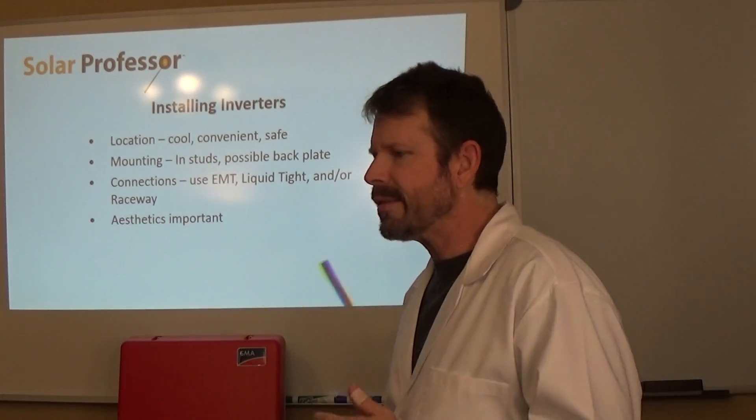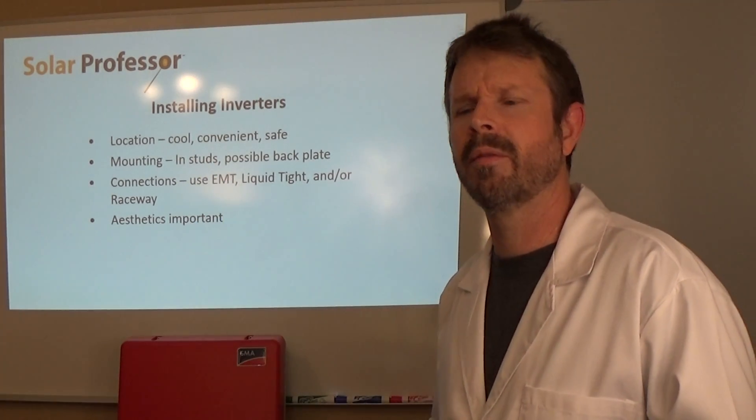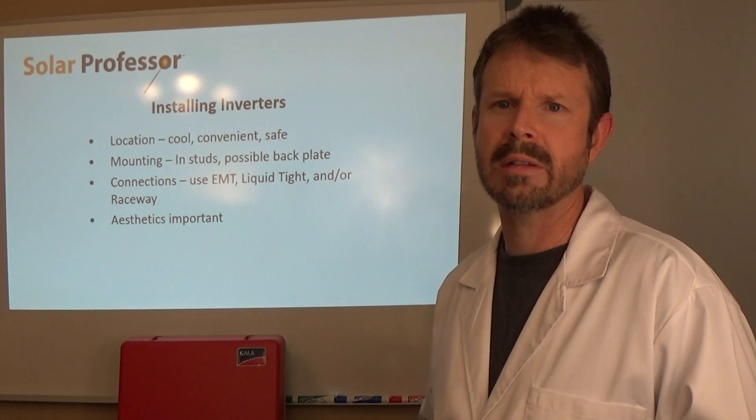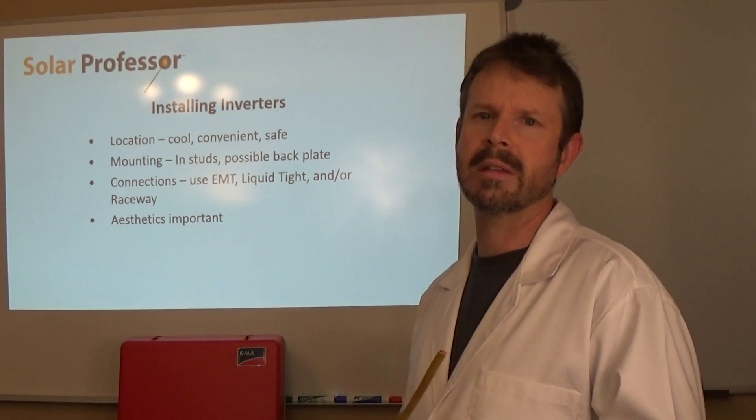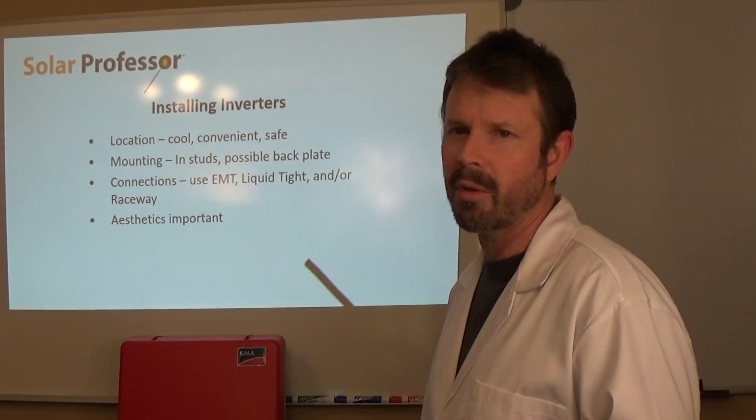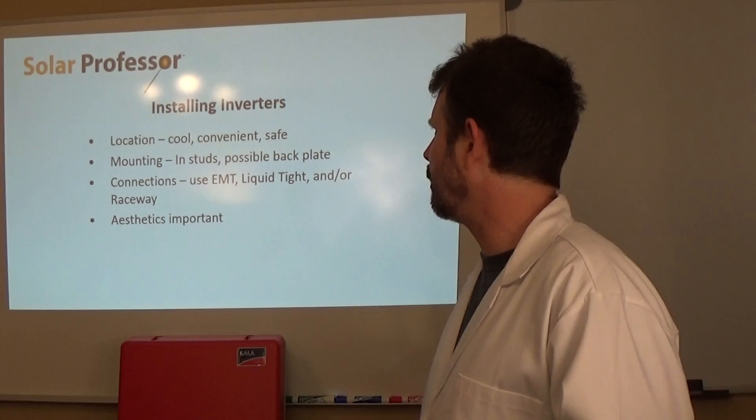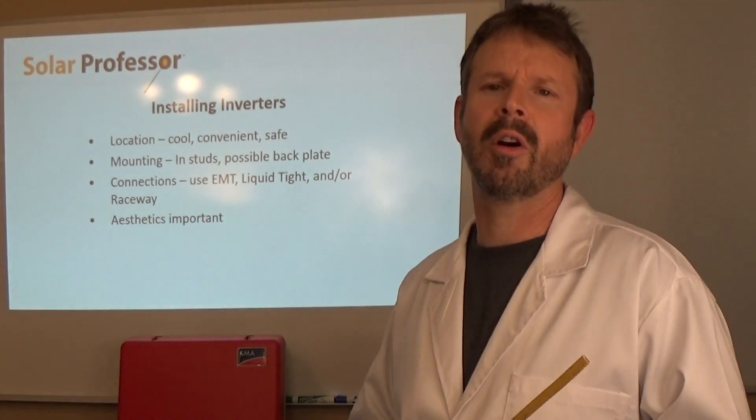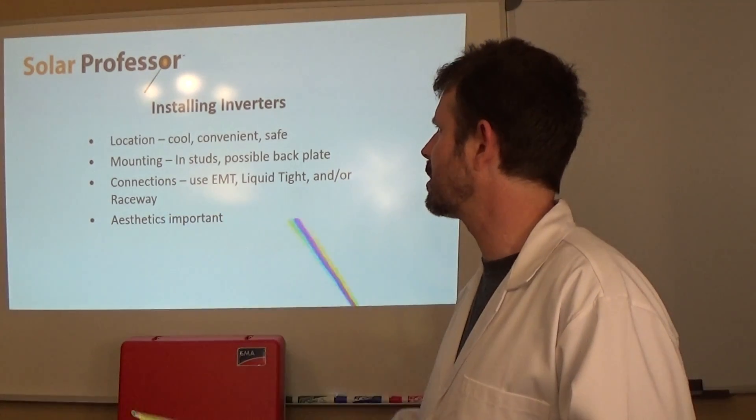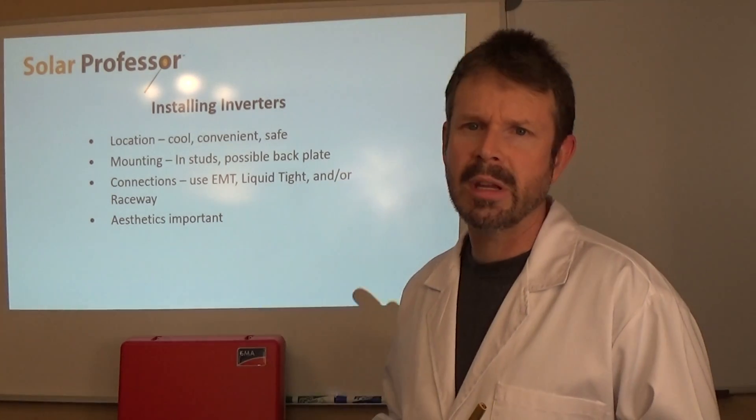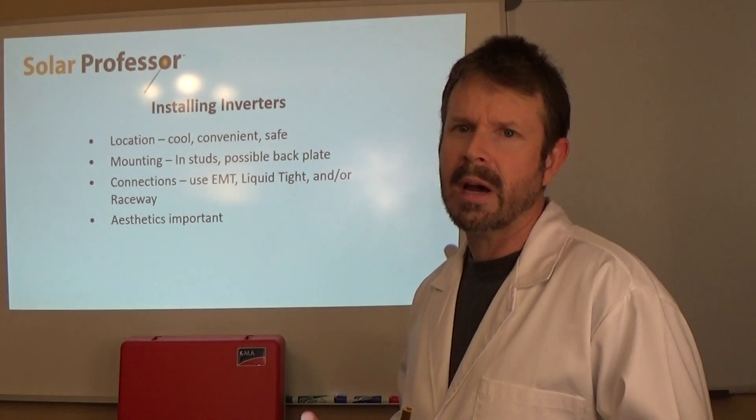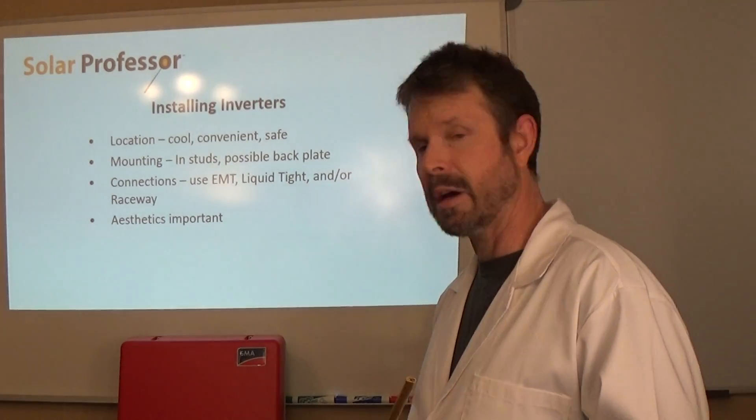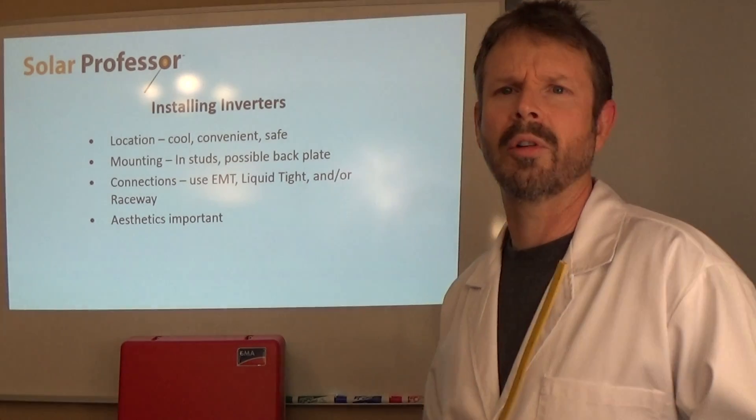Mounting, sometimes the inverters are heavy. The older inverters had transformers in them, transformers are really heavy pieces of componentry inside the inverter. The newer inverters are transformer less, they're a little bit lighter but still we want to mount them so they don't fall off the wall. Connections, we're going to always want to wire properly according to NEC, follow the instructions from the inverter manufacturer, that's a huge deal. Use our raceways, our EMT electro metallic tubing or our liquid tight, those are types of conduit for installing our inverters.